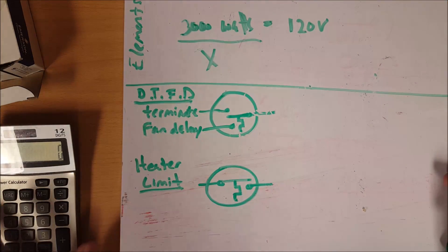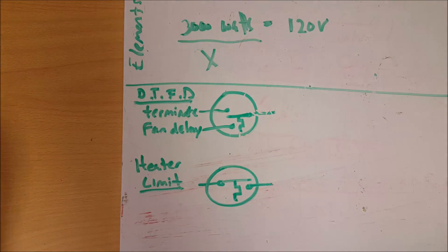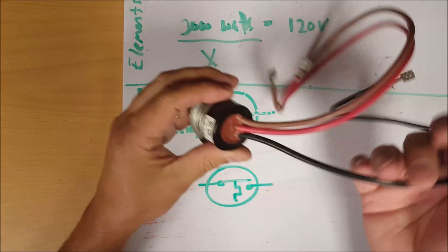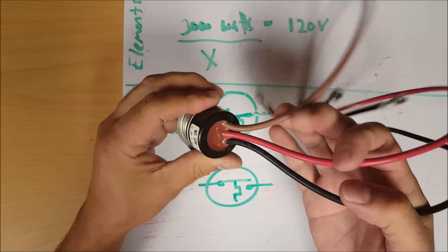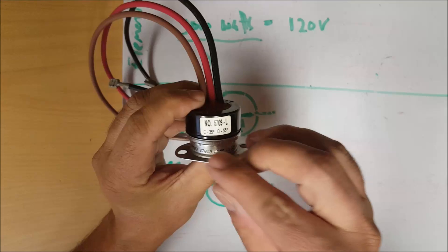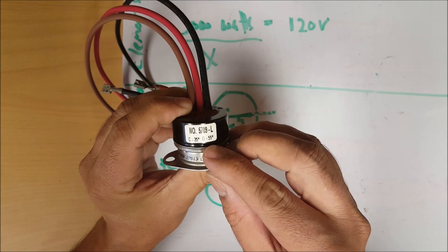Alright, next thing is going to be the defrost terminator slash fan delay switch. I have one right here. Basically it's a three wire switch with a black, red, and brown wire. If you look here on the numbers it's got C 35 degrees and O 55 degrees.